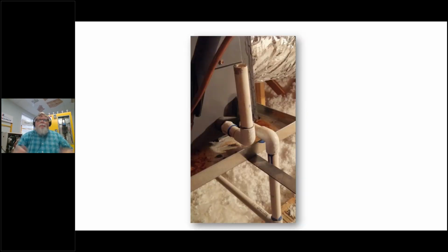Here's a guy in the attic, big pipe turned up on the secondary drain. All they're doing when this unit is running is sucking hot, humid air out of the attic. In the case of Virginia Beach, that air is probably 135, 140 degrees in the attic. It's got high humidity. You're putting it in the equipment and adding to the load that the unit's having to work on. It's not doing the job.